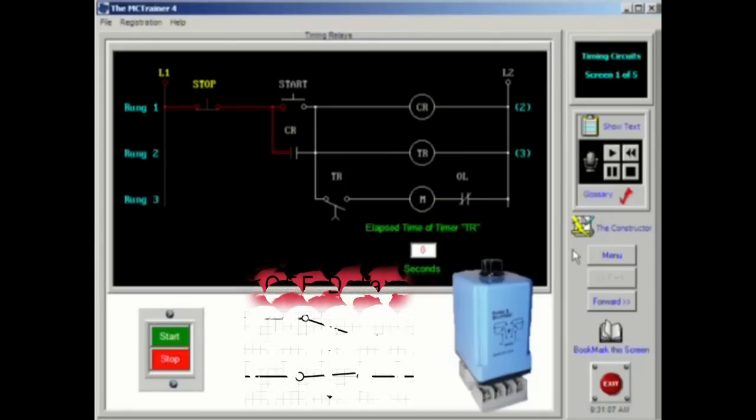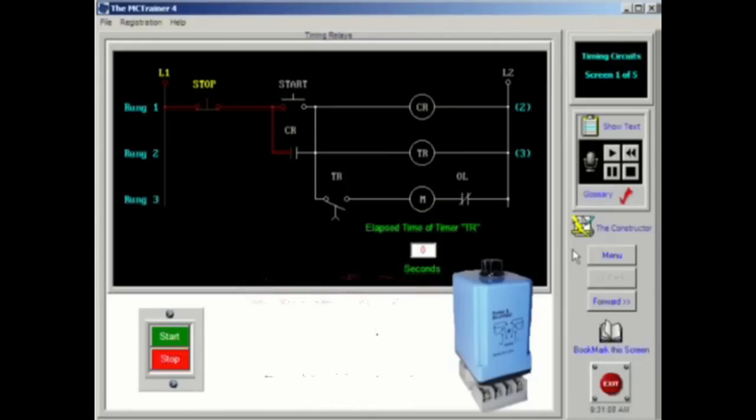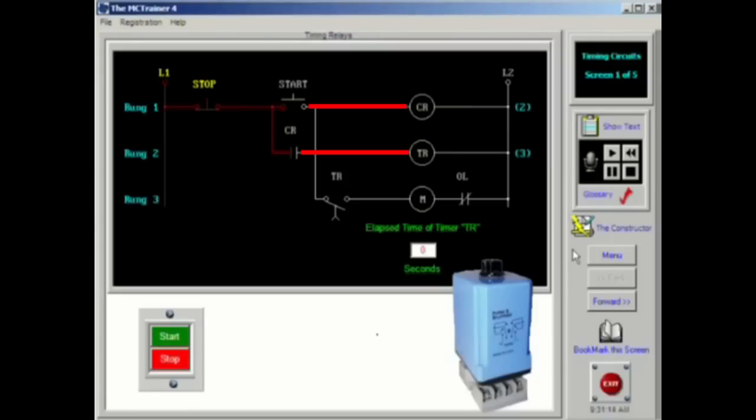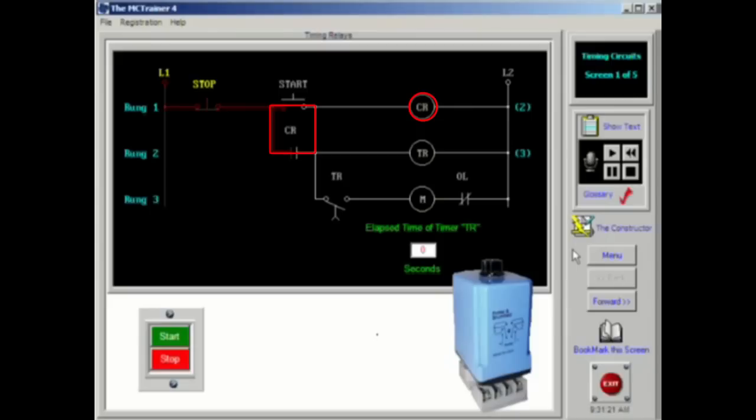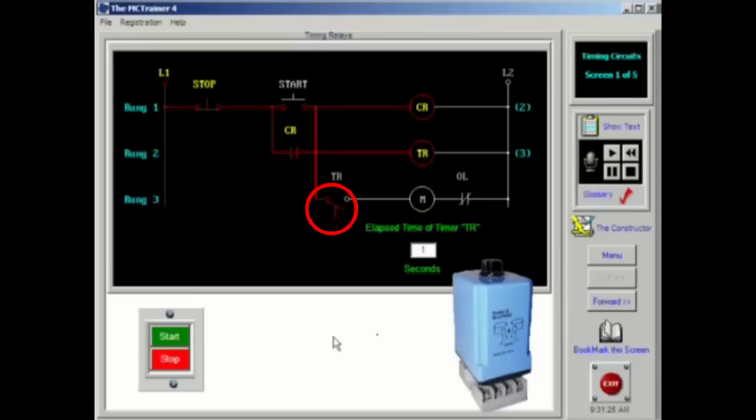The diagram shown above is a typical application for an on delay timer. When the start button is pressed, both the control relay and the timing relay are energized. The control relay is necessary to accomplish seal in. When the timing relay times out, the normally open, timed closed contacts will close and energize the coil of the motor starter.